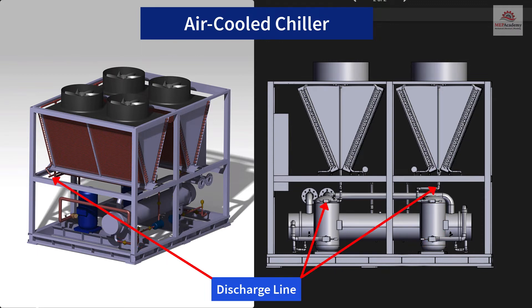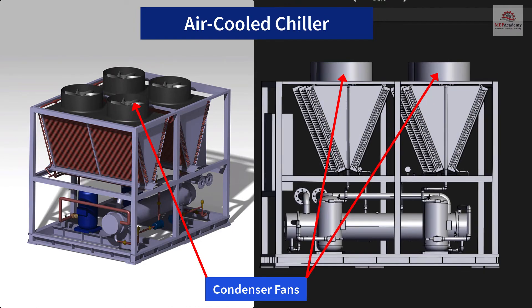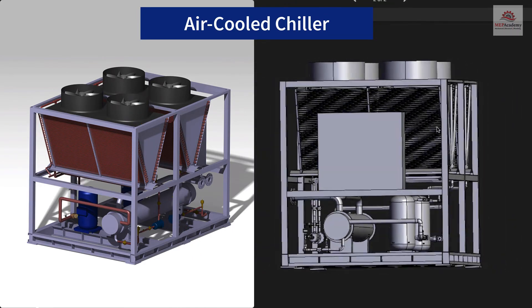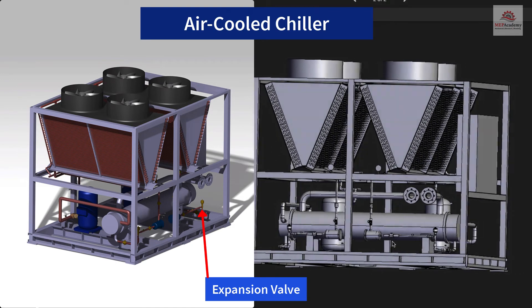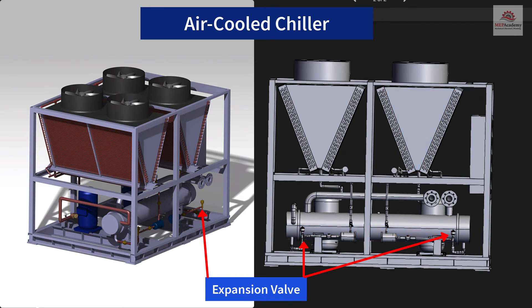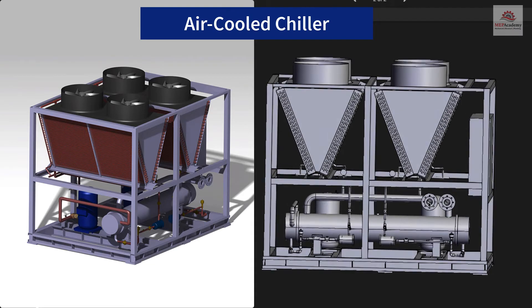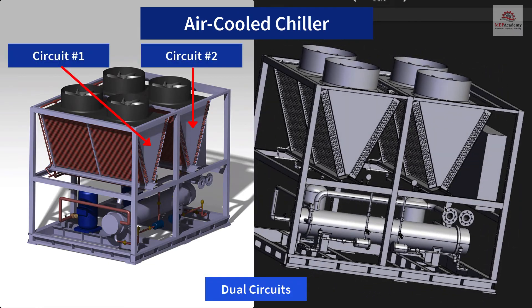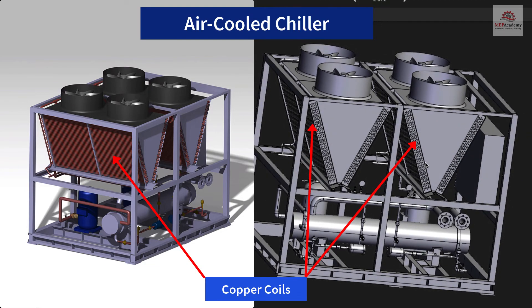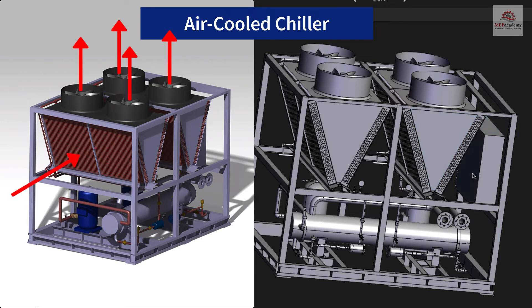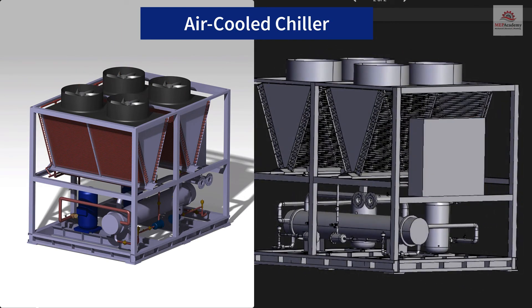From the compressor, the hot gas discharge goes into the air-cooled condenser coils, with fans on top. The unit has a dual circuit design with two separate circuits, each having its own compressor and expansion valve to control capacity. The condenser coils are copper with aluminum fins. Air is drawn in from outdoors over the coils, and the heat is blown straight up and out. This unit is located outdoors.